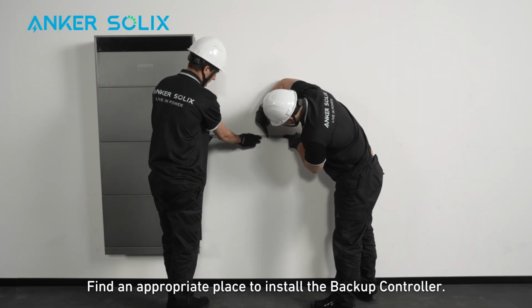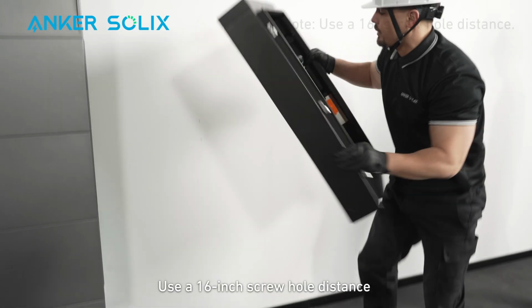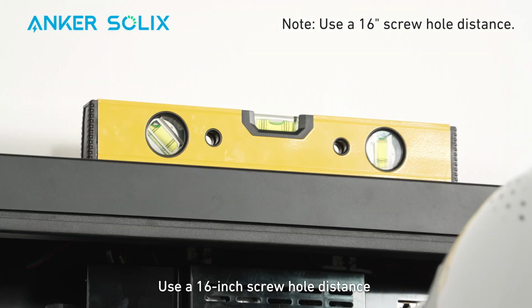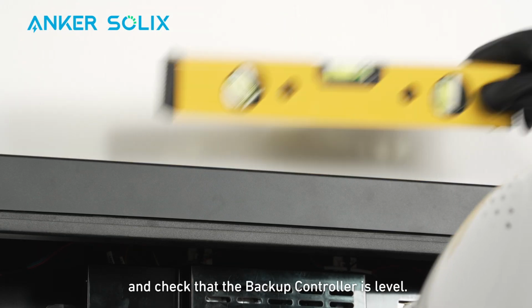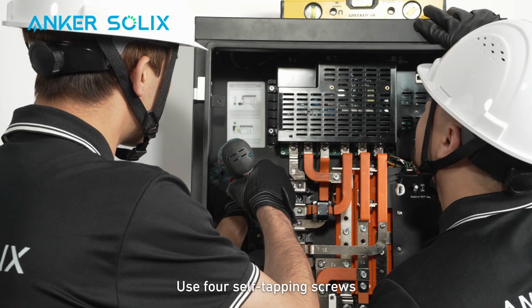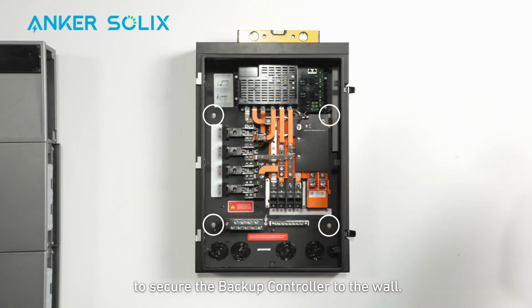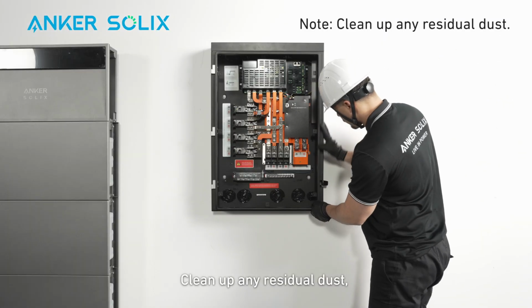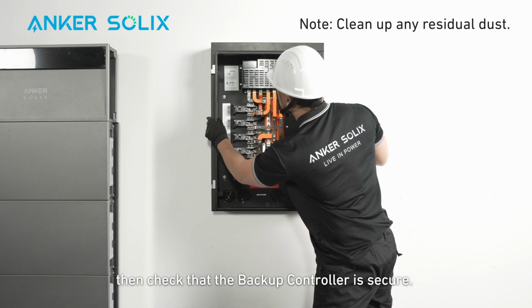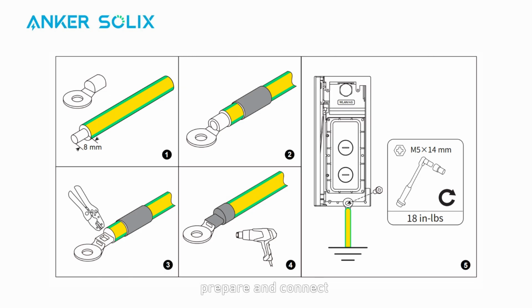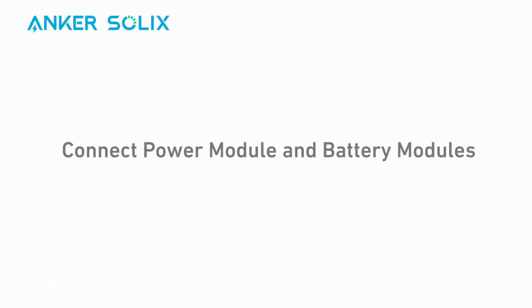Find an appropriate place to install the backup controller. Use a 16-inch screw hole distance and check that the backup controller is level. Use 4 self-tapping screws to secure the backup controller to the wall. Clean up any residual dust, then check that the backup controller is secure. Now, you can begin wiring. First and foremost, prepare and connect a ground cable from the power module to the external ground point.